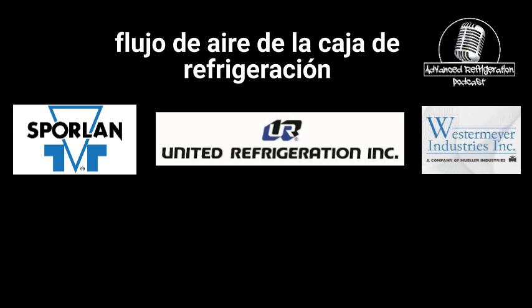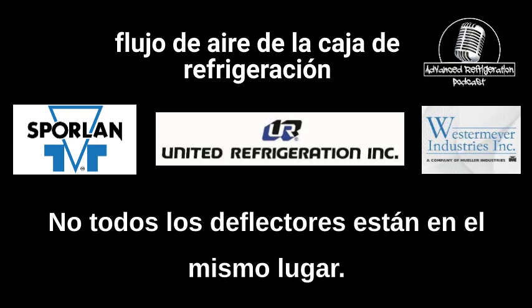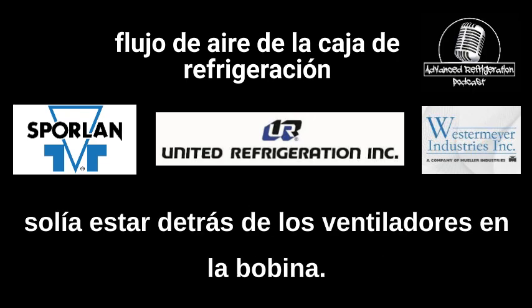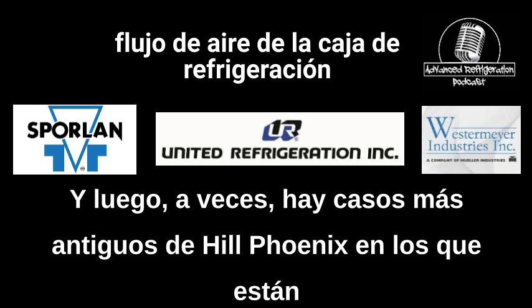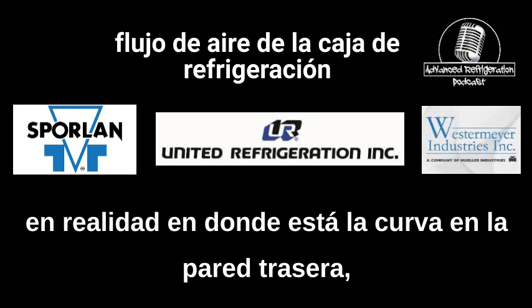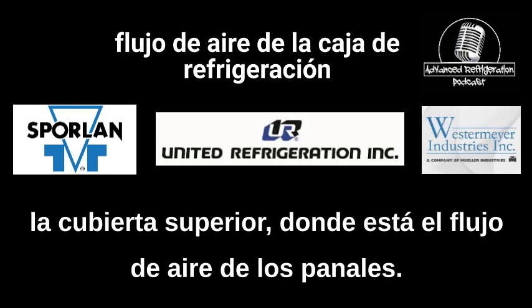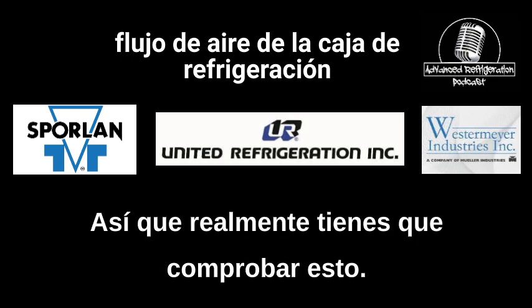Go ahead. So with those baffles, I just want to throw this out here, guys. Not every baffle's in the same place. Like some older Tyler cases, the baffles used to be behind the fans on the coil. Some random cases, they were in the back wall above the coil. And then sometimes there's older Hill Phoenix cases where they're actually where the curve is in the back wall, where you have your transition from the back wall to the upper deck where the honeycombs airflow is. The baffle's in there. In some Hussmann cases, the baffle is literally behind the honeycombs. So you really got to check this out.